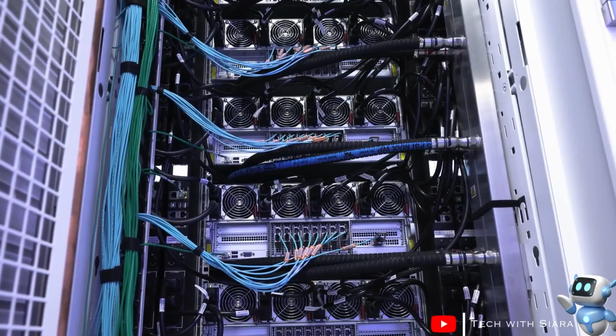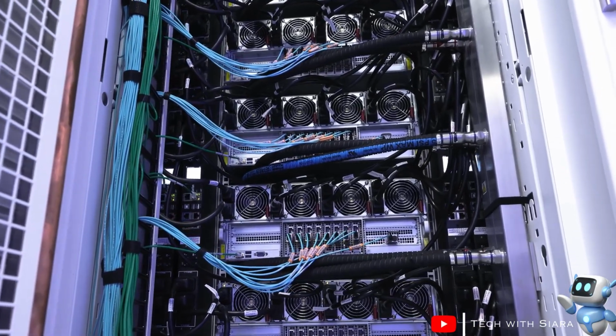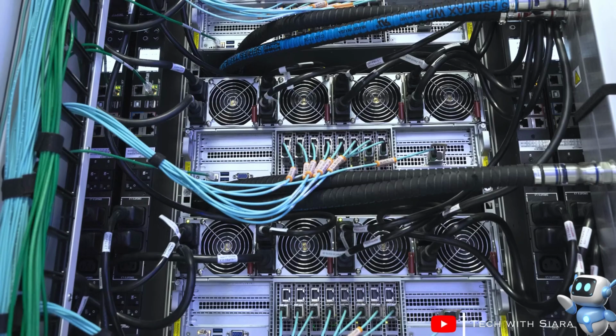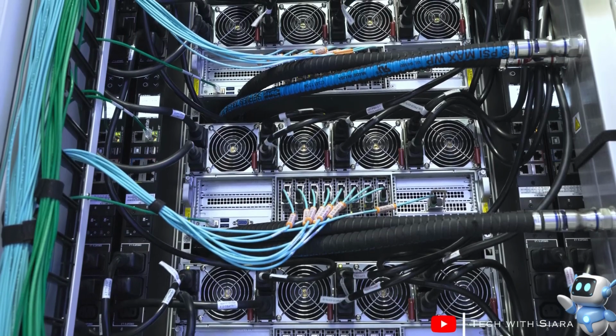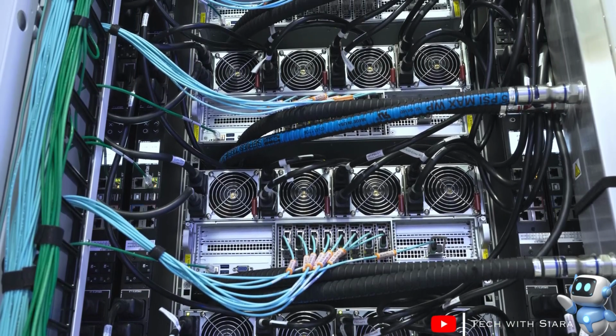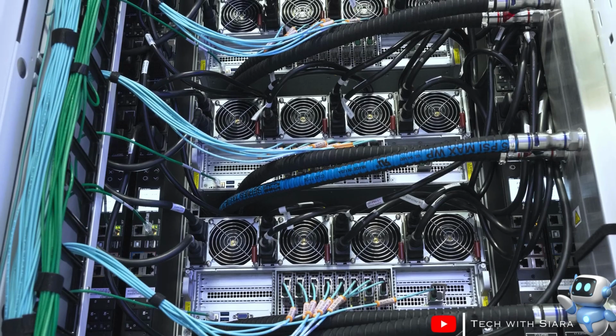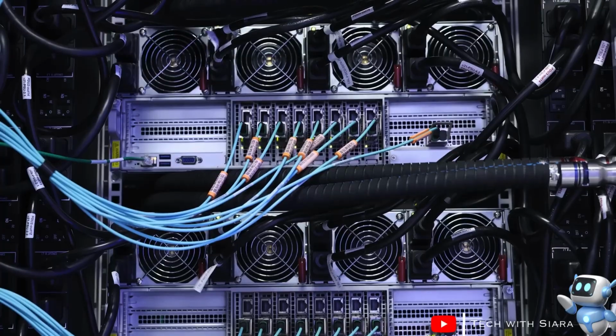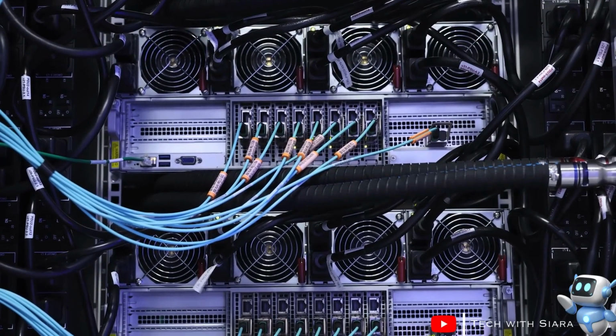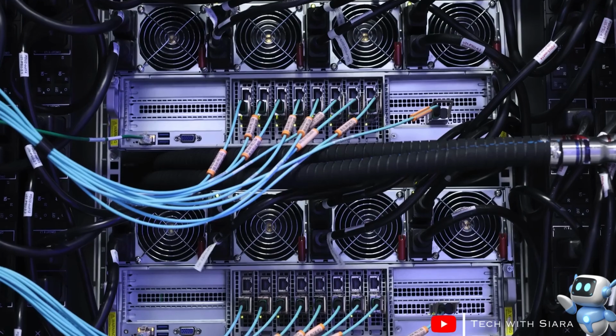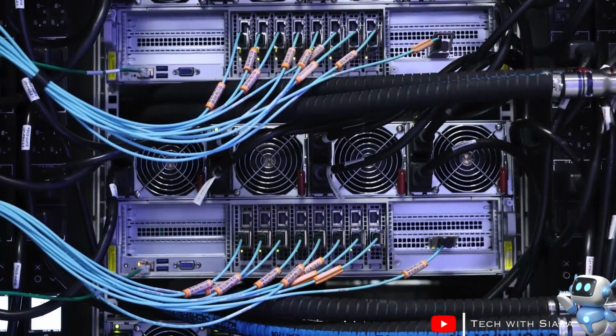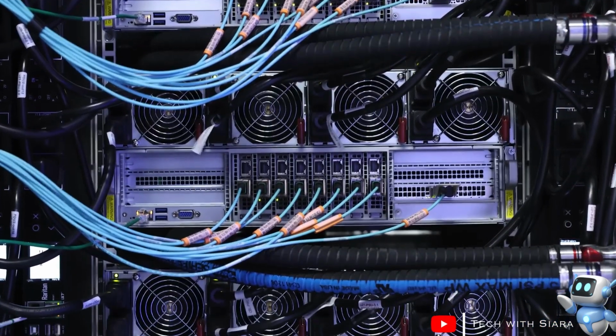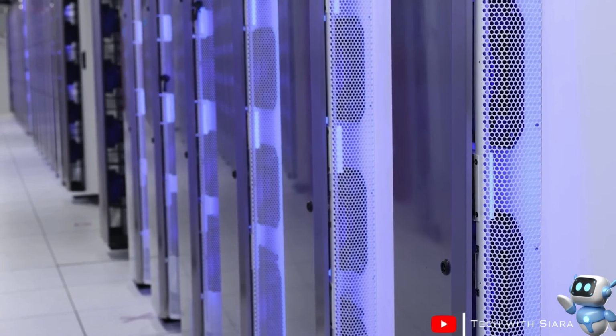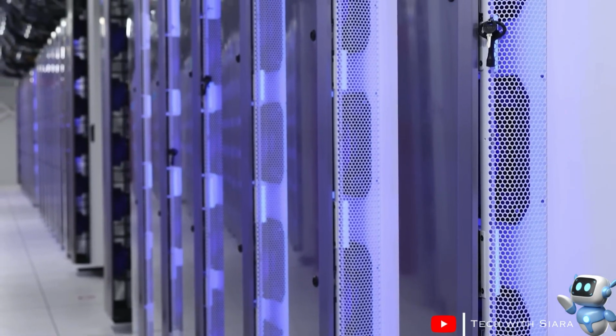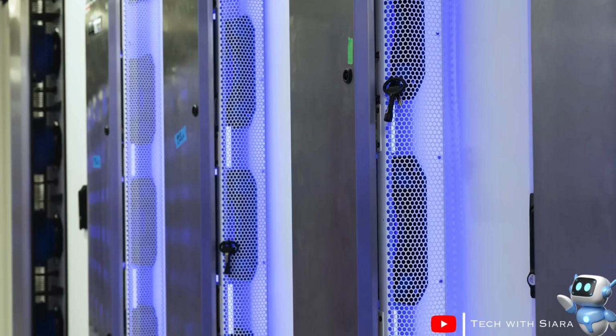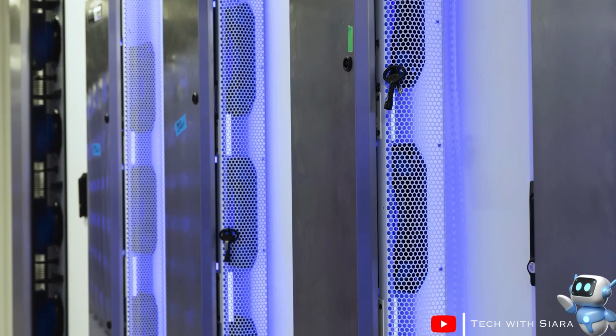Now let us go to the back side of these racks. At the back there are many fans and network elements. The question is, if the GPUs are liquid-cooled, why are these fans needed? Well, the liquid cooling system only cools the GPUs, but to maintain the overall temperature of the rack and cool down other components like memory, these fans are required. We have a heat exchanger in the rear doors of the racks. It passes hot air from the internal fans through the radiator and flows cool air back into the rack.